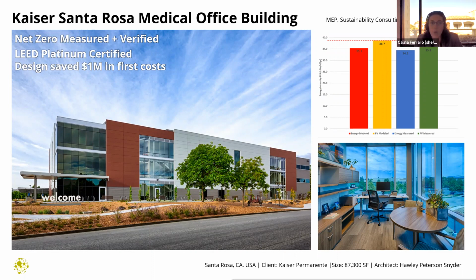When we talk about high performance strategies, they often get dismissed as not being in the budget, or people say that's a premium product, we can't do that here. I think this is a really good example of where, when we really buckle down, we didn't use a crazy system - it was still just packaged units on the roof. But the way we zoned it, we were able to eliminate some of that reheat, which is often just treated as a baseline assumption that of course you would have. So it's really about challenging the way we design conventionally, doing it differently, and taking advantage of those savings to incorporate other elements that would often be seen as an add, like the on-site PV here.